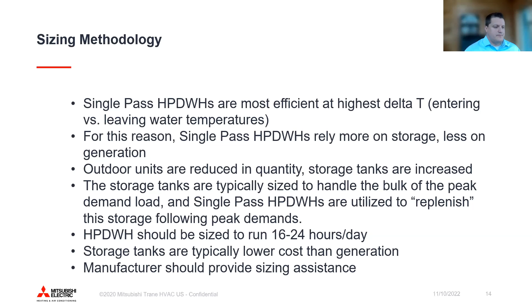It's just a rule of thumb, but it is something that we shoot for, mainly because storage is more cost effective, but also because it helps you in different utility situations to look at peak demand and ratchets and stuff like that as you may see fit. Ideally, our system is going to run almost all day, 24/7. You really want to keep that system running throughout the day as much as possible. You'll see in some of our sizing tools when we get to the end here, we target 16 hours or more if possible, and any of your peaks are taken up by the tank sizing.